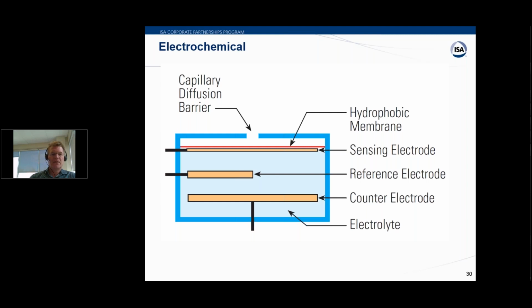And of course, the thing with electrochemical is that by picking the right combination of electrodes and electrolytes, we can select the gas that we want to measure. So electrochemical are not only used for LEL, but they're also used for things like H2S, SO2, ammonia, specific gases. And the resistor across the electrodes gives us a current proportional to the gas concentration. Response time here is typically about 50 seconds. Relative humidity up to 95% non-condensing.